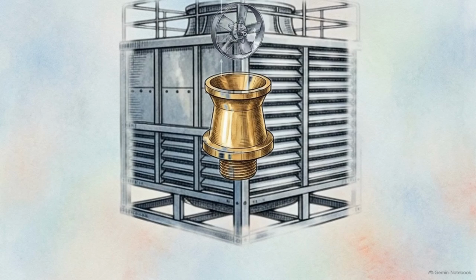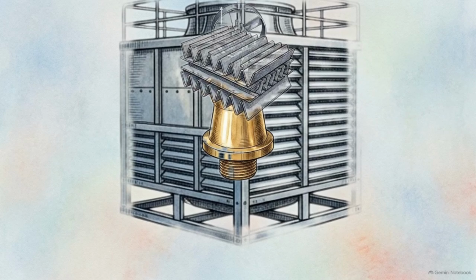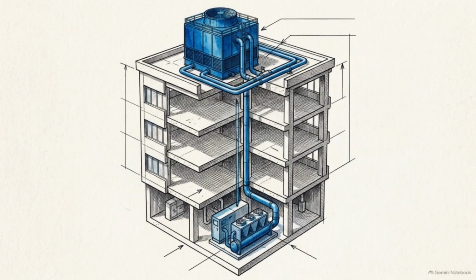This induced upward draft creates a mechanical loss. High-velocity air will physically strip small droplets from the spray and carry them out into the atmosphere, wasting treated water. To prevent this, engineers install a mechanical baffle called a drift eliminator. Escaping droplets strike this corrugated layer, condense, and fall back into the system. Gravity pulls the successfully cooled water down into a large collection basin at the base of the tower. From here, return piping routes the cold condenser water back down to the chiller, completing the thermal bridge.